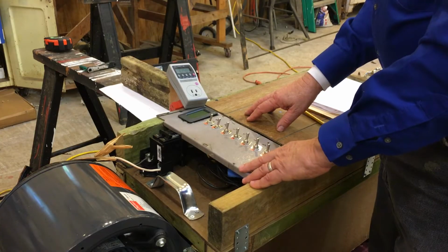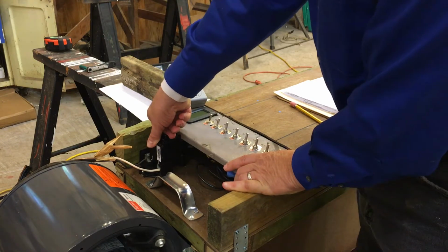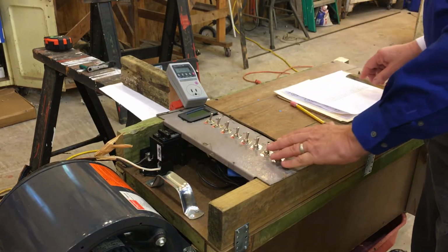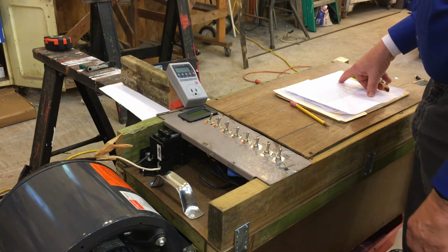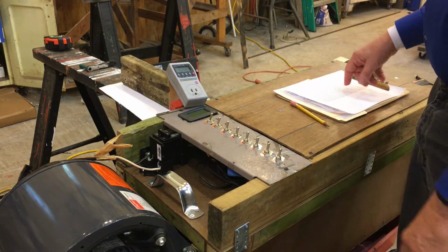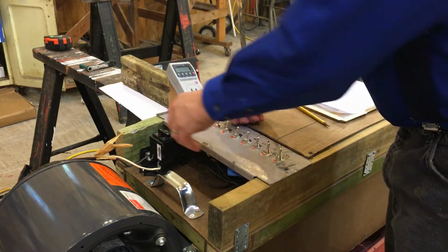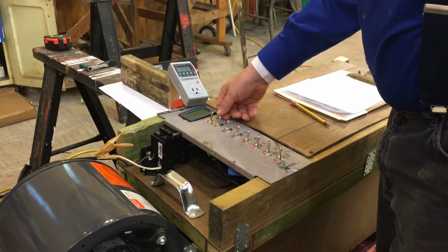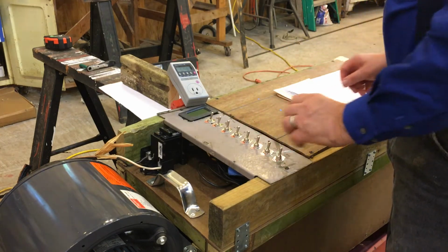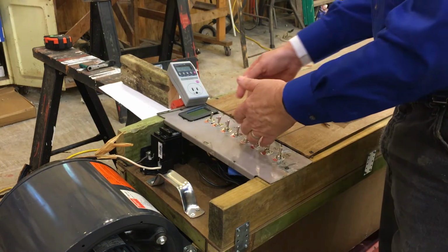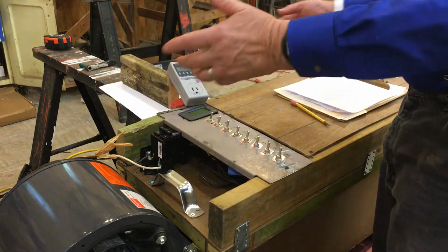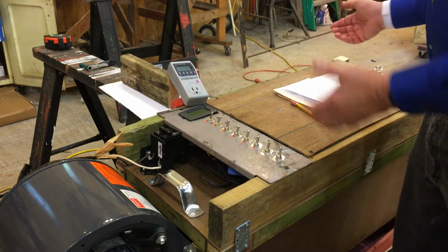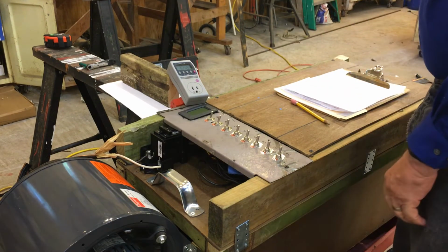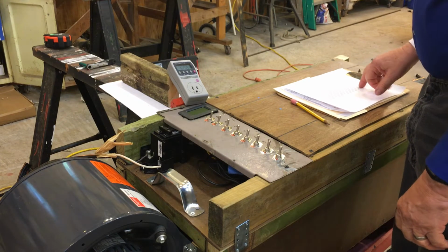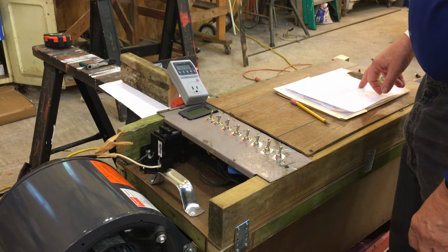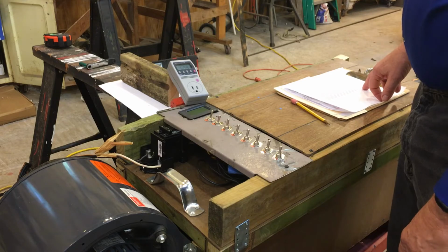The procedure that you'll see will be, I'll apply a load with all the switches in the off position. The load will probably be about 139, 140 watts. I'll record that, then after I shut the power back off, I'll reset the switches, change probably to around 600 watts, turn the power back on. I'll read the meters, record that just with a pencil. And finally, we'll be getting up into the range of 3,000 plus watts on up toward 3,600 watts, and we'll see how the generator does.